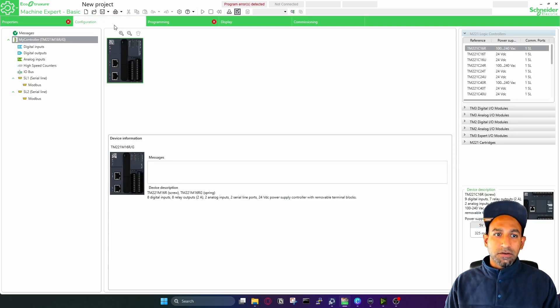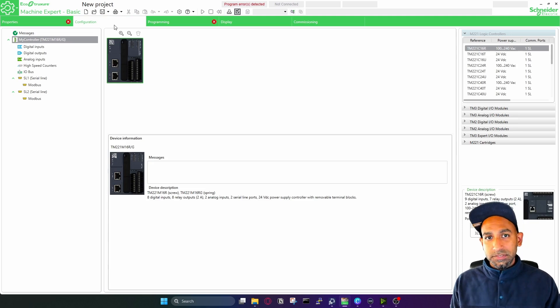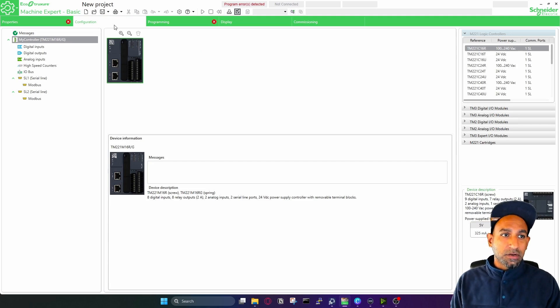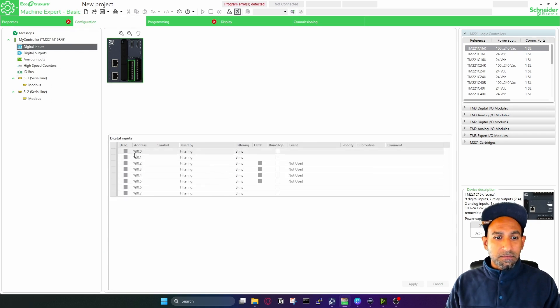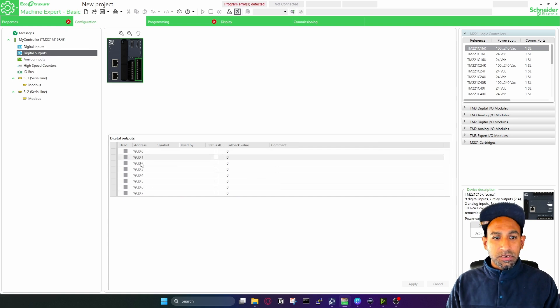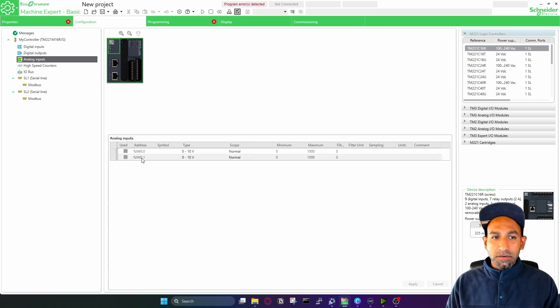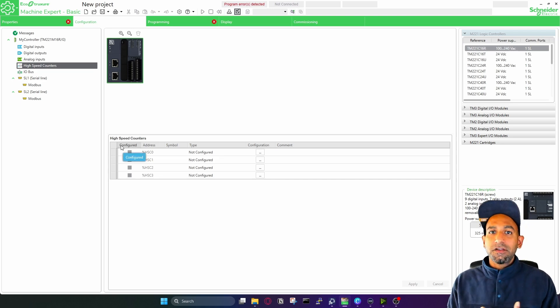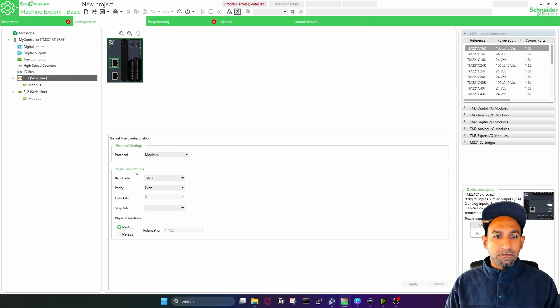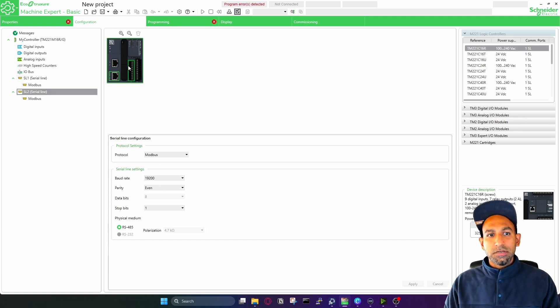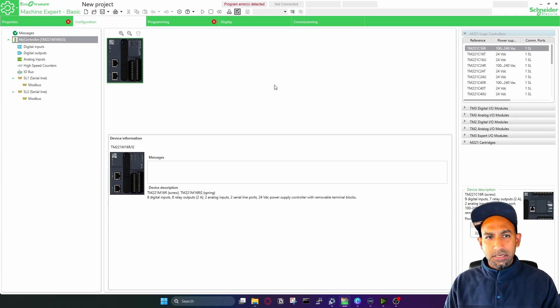Then you have the configuration section. In configuration you define which hardware you're using and the IOs of that hardware — digital inputs, digital outputs. Here you can define the symbol of your IOs, which already have addresses. Inputs go from I0.0 to I0.7. Then you have digital outputs, analog inputs, and high speed counters. You can also configure the controller — for example, the serial line and Modbus communication settings.